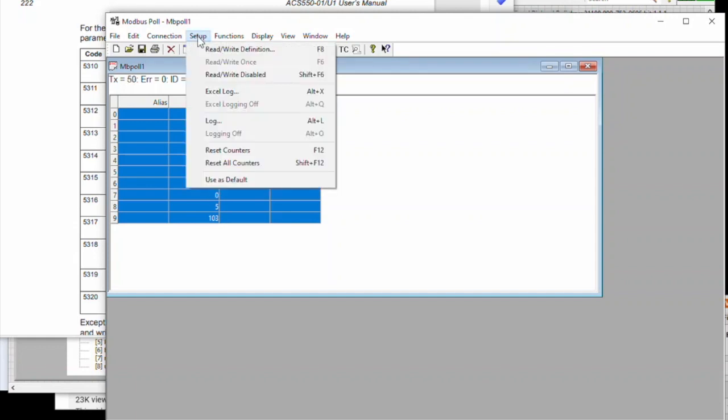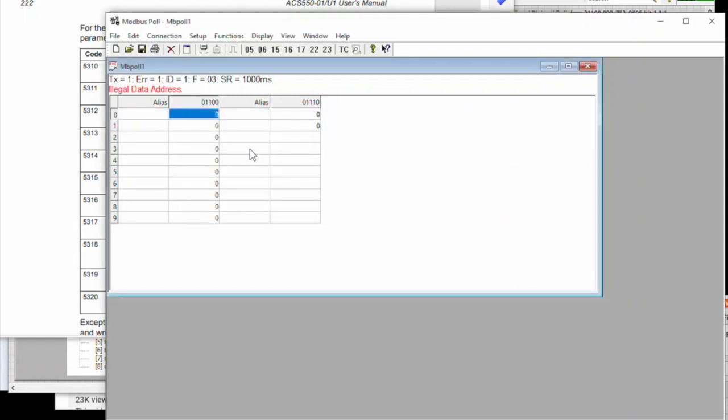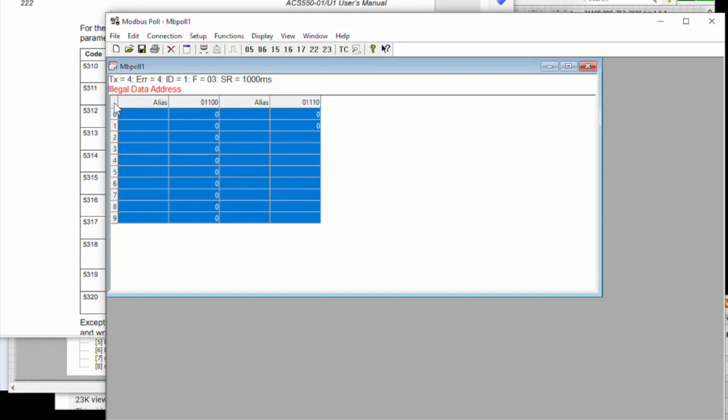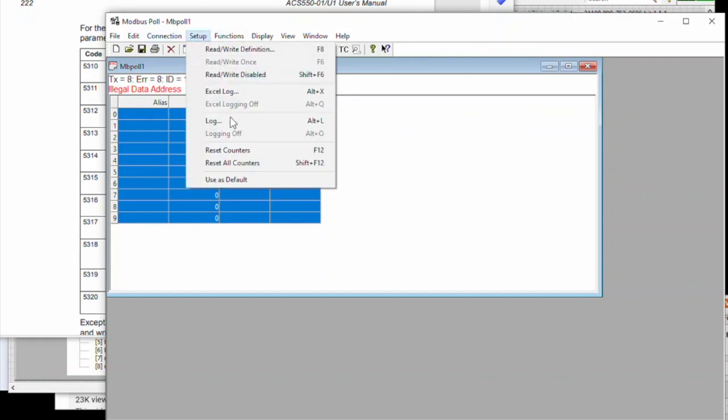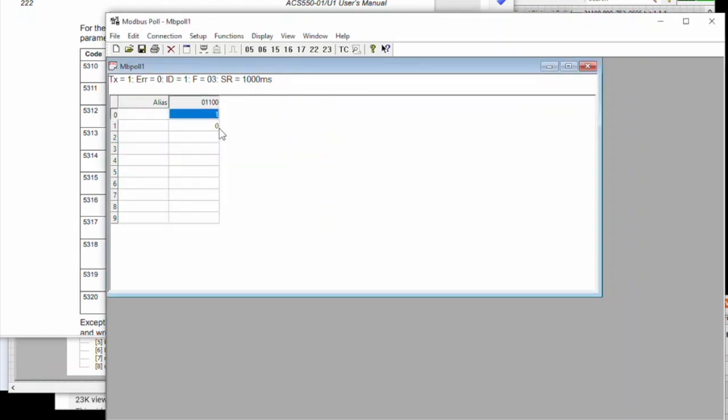So here's how you could read the parameters living in the setup 5300. So now we're going to look at the setup of 1,100. 1,100 is where you set up your modbus. So 1,100 can only take two elements set up. We're looking only to read two. If you read too many, you get this invalid data. There we go. So 1101 is a 1, which means field bus modbus RTU. This is where it receives the instructions. And 4 is 0.